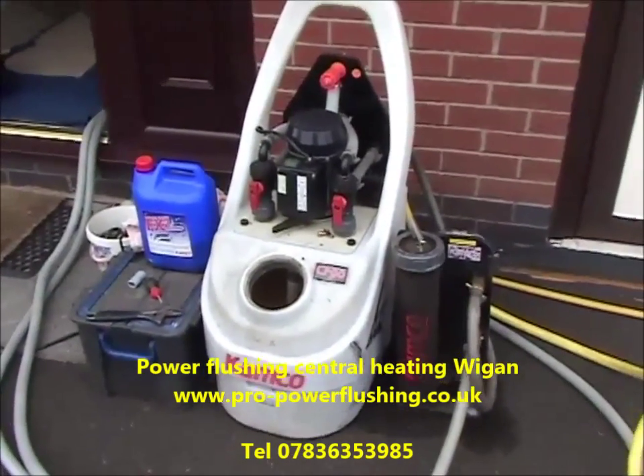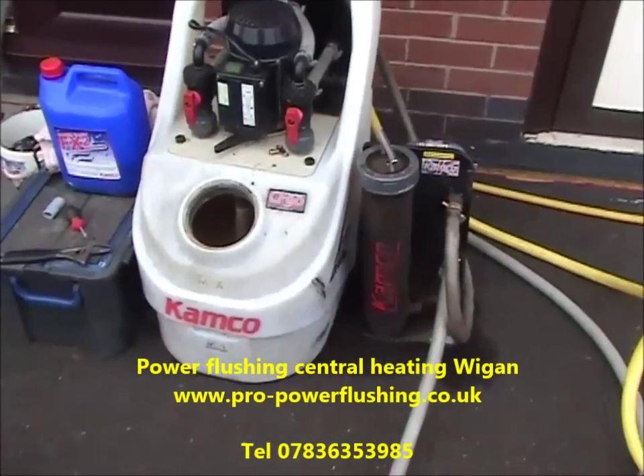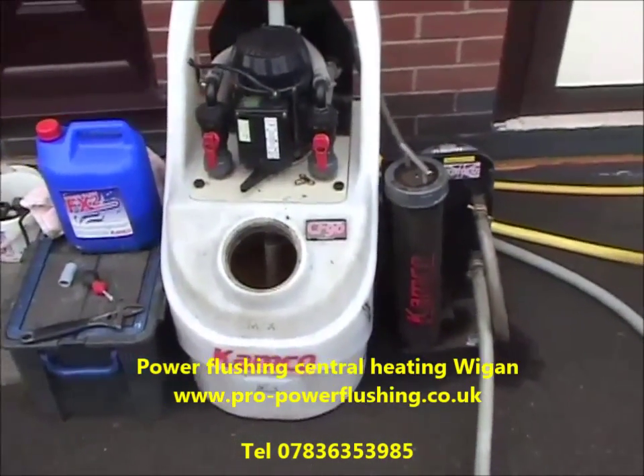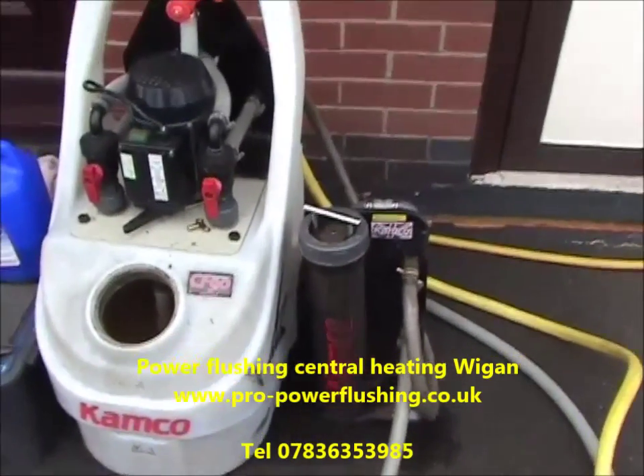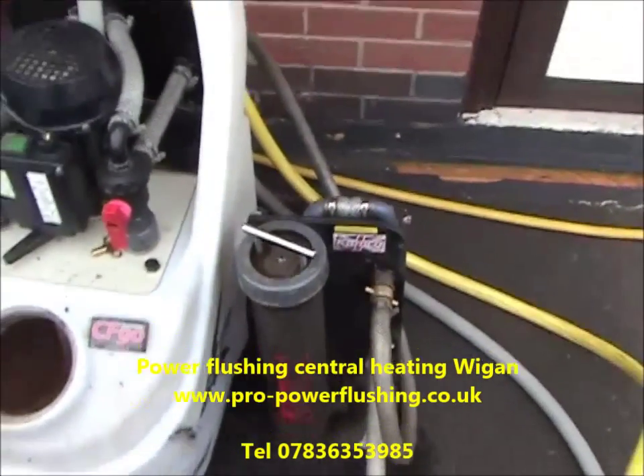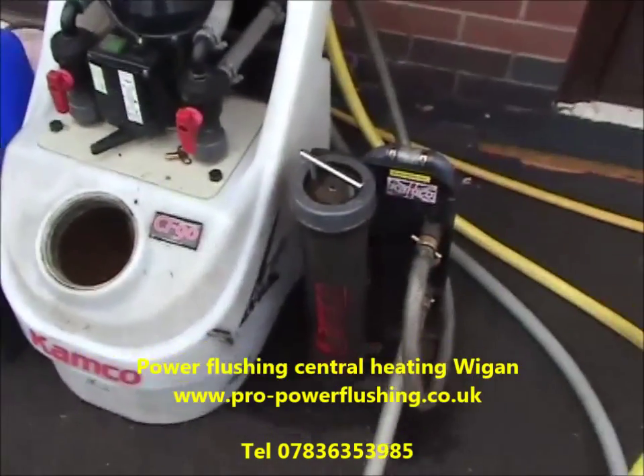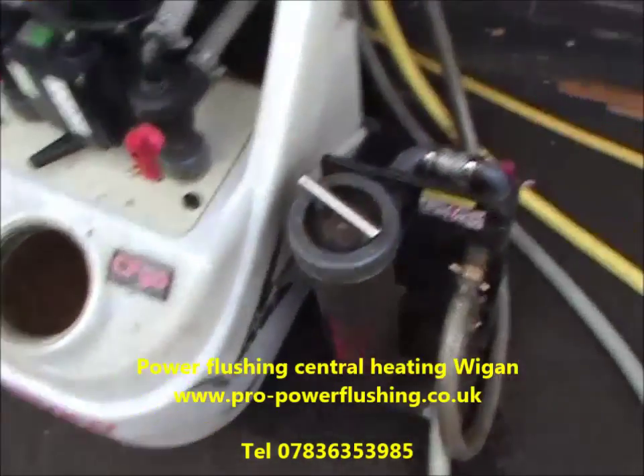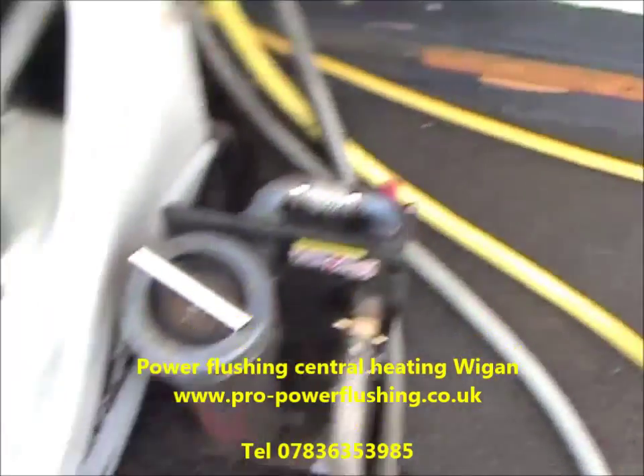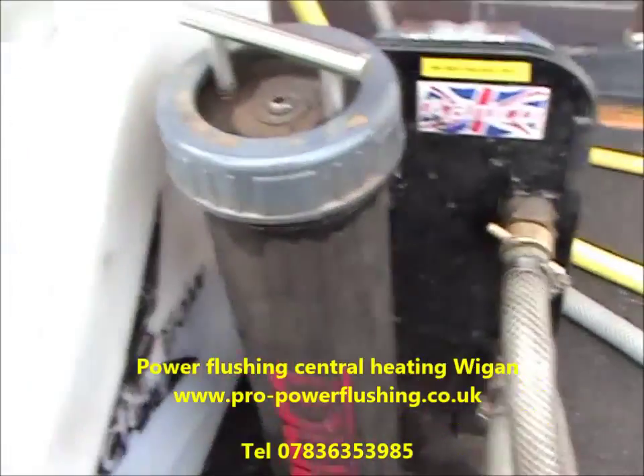Okay, we've managed to get some heat into the system, get some chemical in. We're going to put the magnet on bypass shortly and show you that. Okay, we've just put the magnet on bypass. Now I know even before I open this magnet that it's going to be full of rust and corrosion, because of the amount of metal in this system. There's some of the rust there. It's still the colour of water, still breaking the rust and corrosion down in this central heating system.